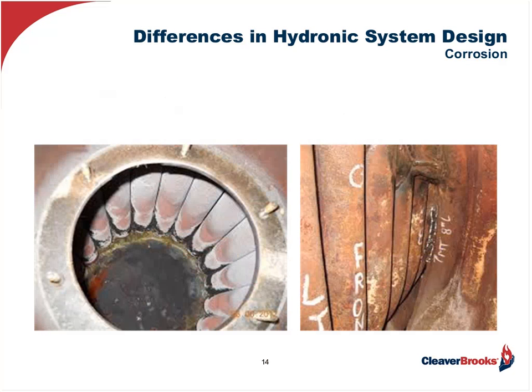Again, remember I talked about condensing mode. What happens with a conventional boiler is you're going to get condensing. Now, in a condensing boiler, as we'll talk about, they're made for that. But in a non-condensing boiler, a conventional fire tube or water tube that's made out of carbon steel, the condensation is going to cause deterioration and ultimately failure of the boilers. And we can't get the high efficiencies without using condensing boilers.